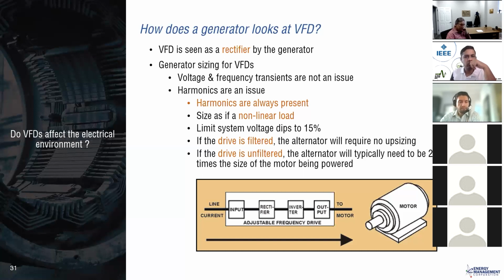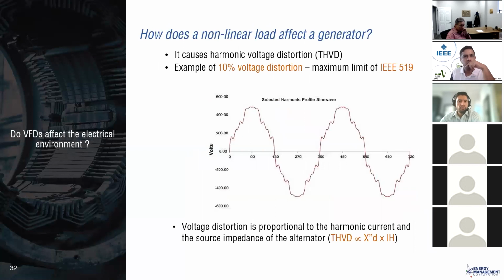And 15% voltage dip tolerance impact the size requirements for any across-the-line starting motors in the system. And coming to the main point here, 15% distortion tends to result in application issues. So we see that IEEE 519 has 10% voltage distortion as standard. So the voltage distortion is proportional to harmonic current and the source impedance of the alternator.